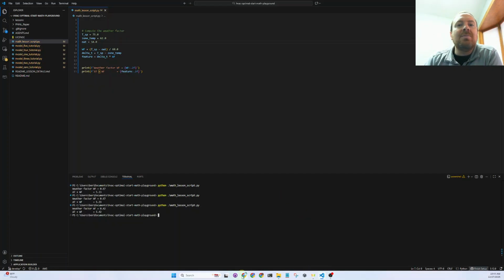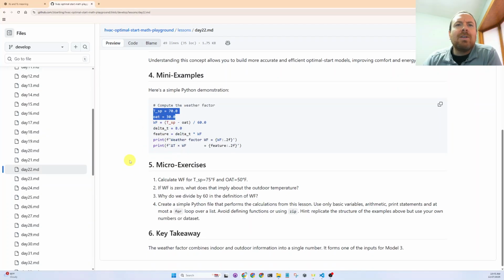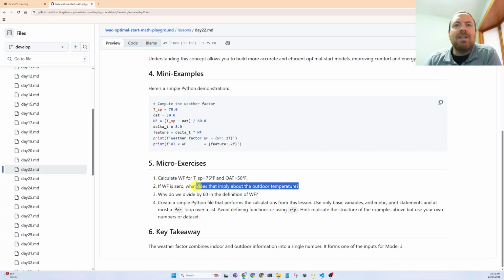So I think that would just mean that if the outside air temperature is really mild, usually 60 degrees outside, the building sits at low 60s, almost 70 degrees Fahrenheit. The temperatures aren't going to drift much inside. So we don't need any outside air temperature adjustment factored in for optimal start.